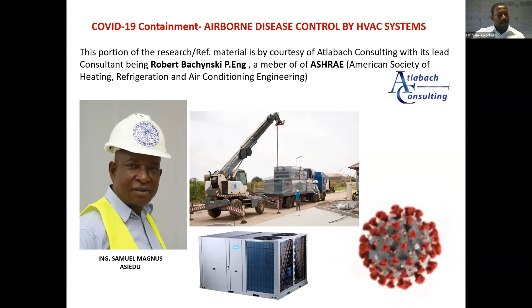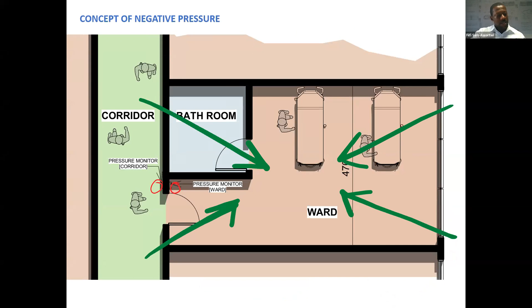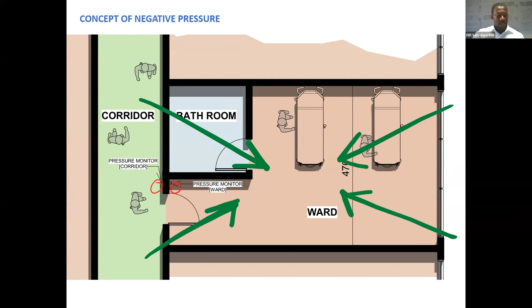So broadly, we adopted a negative pressure concept for our HVAC design, where patient rooms have negative pressure, or better put, lower air pressure than in the corridors. This concept is to prevent used air in the wards, which is expected to be contaminated, from getting into the corridors where healthy hospital staff would be commuting. By this, we have pressure monitors both in the corridors and the rooms, which indicate pressure differences and will set off an alarm if negative pressure is compromised within the wards.